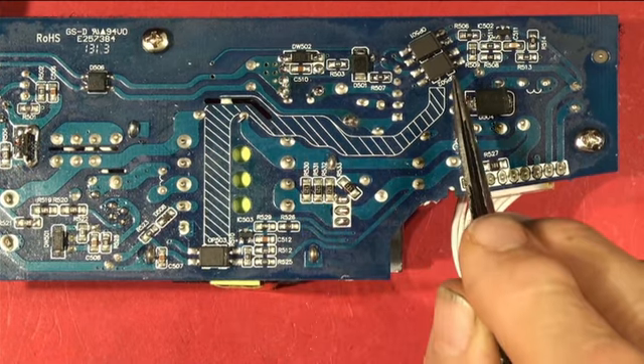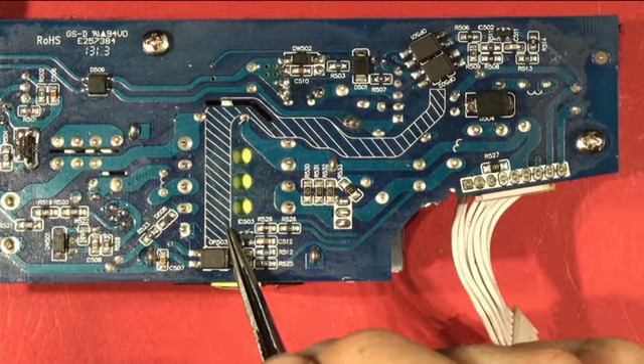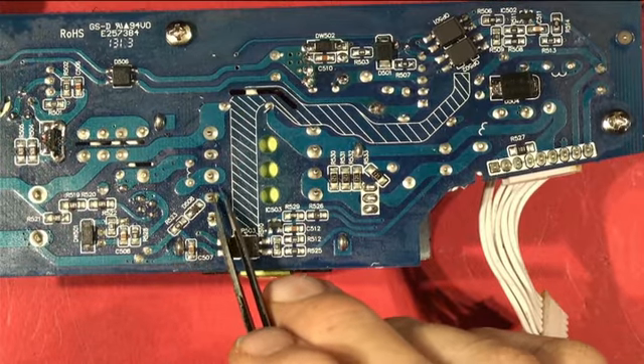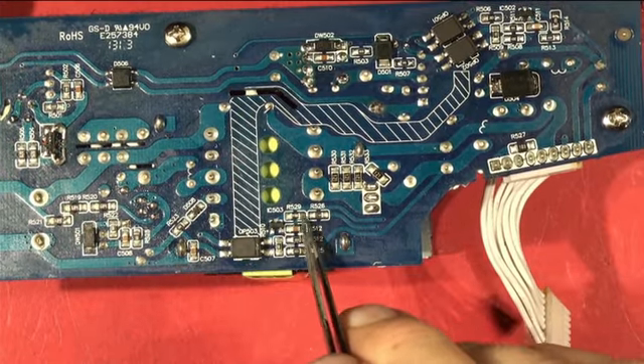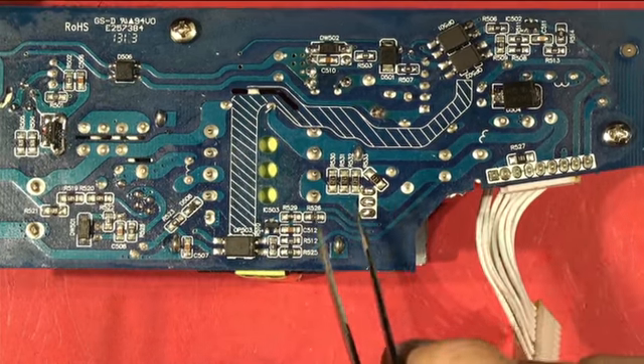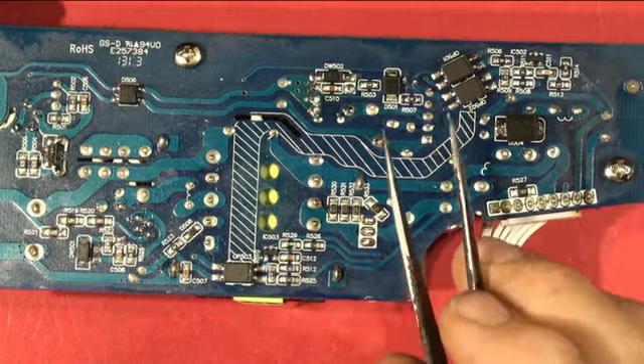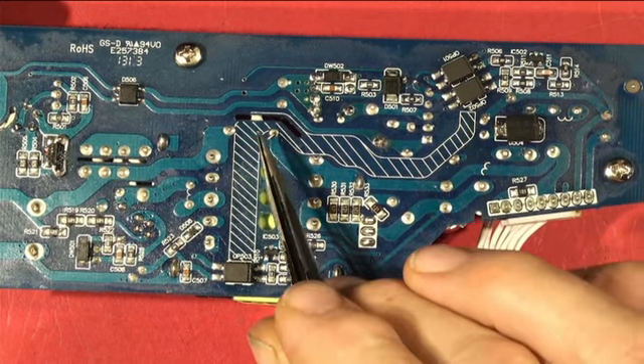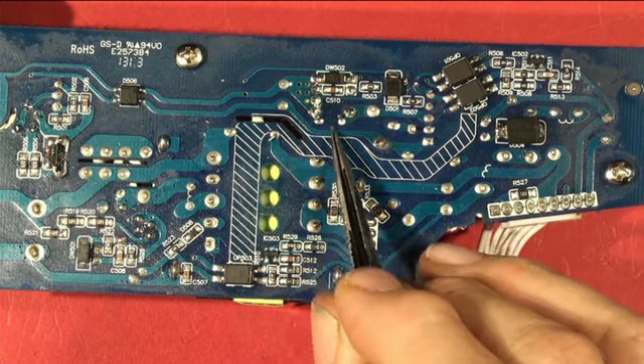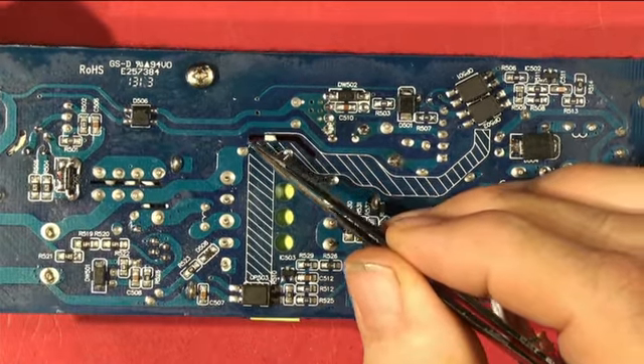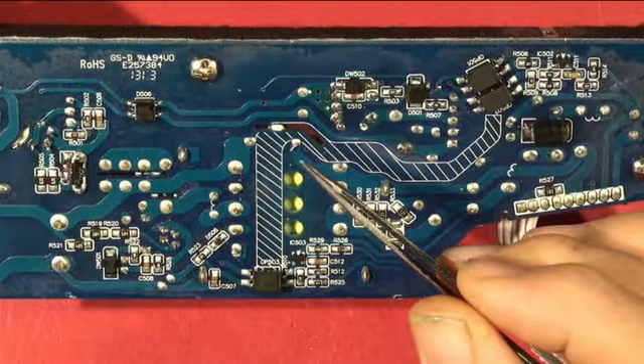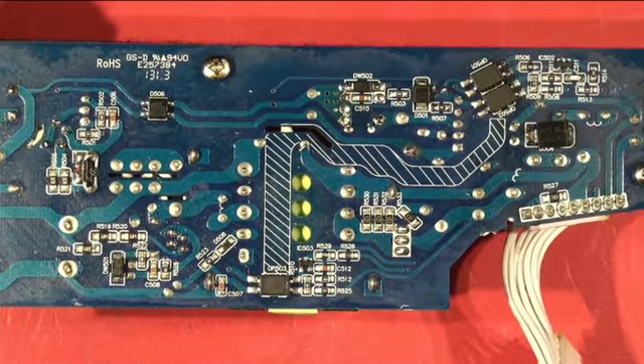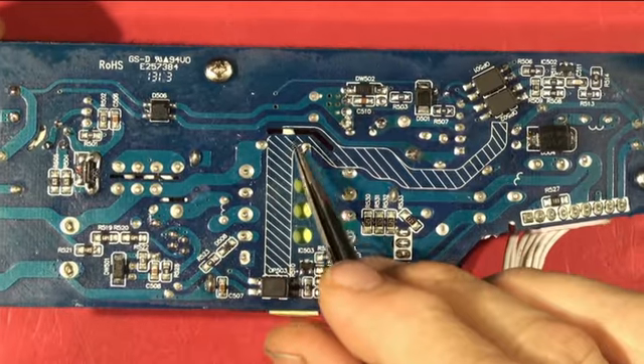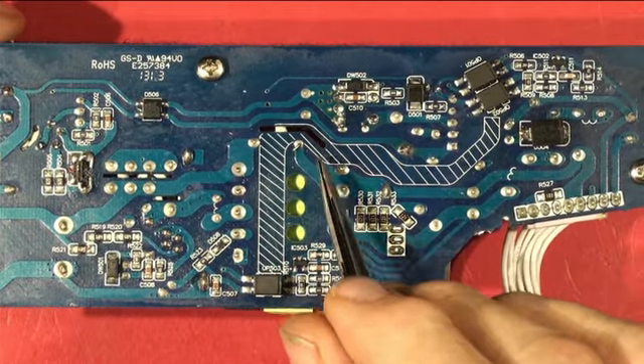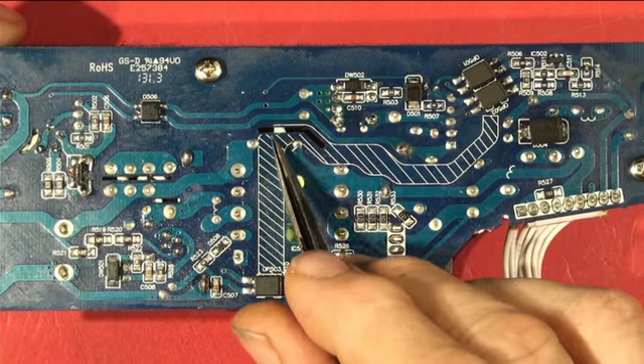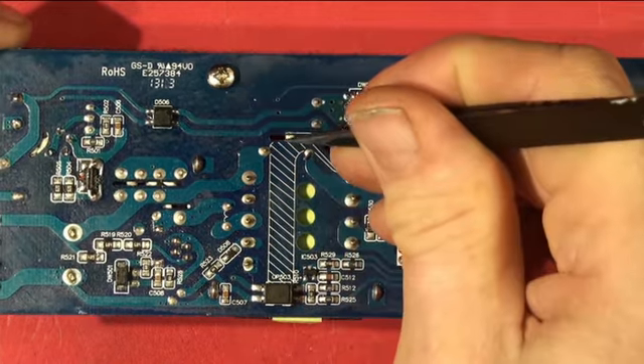So this is the 2 kilovolt isolation channel, which is what you test with a PAT test. You put a high voltage on this side and you check to see if anything's leaking over to the consumer side, and the rules are that it's got to be 2 kilovolts or thereabouts. And you've got this space here, and in certain key areas where it does get a bit close, to improve the isolation you can machine a slot in the board. You can see there's a slot there, goes straight through, and the idea of that slot is to stop moisture or condensation on the board causing this to conduct across. So it's a bit close there, so they put that. Mind you, that blob of silicone won't be helping because that can get wet as well.